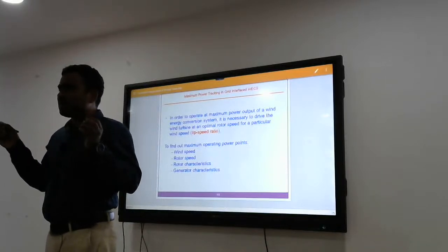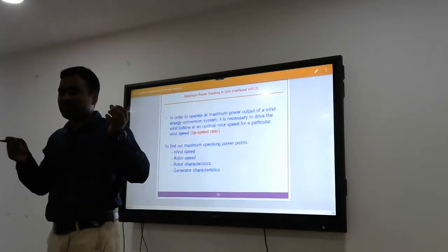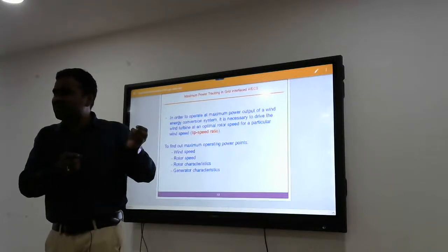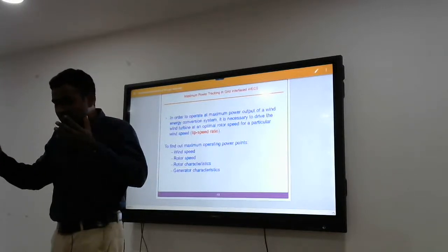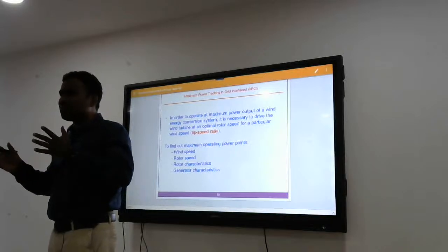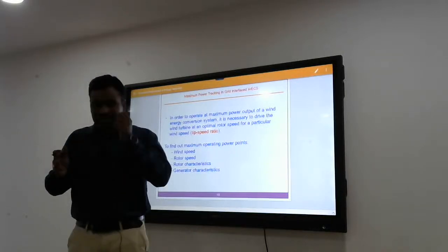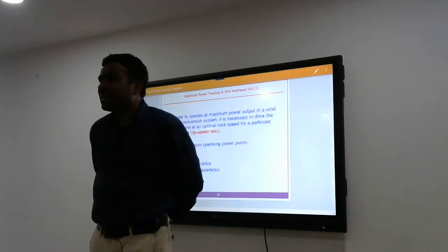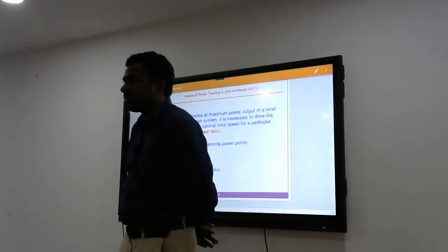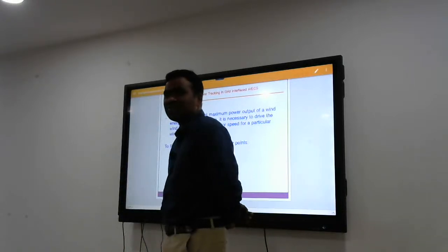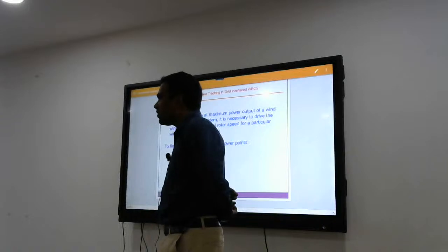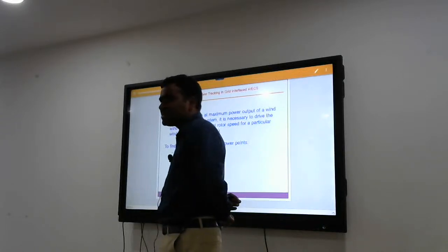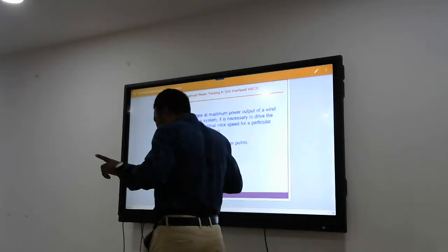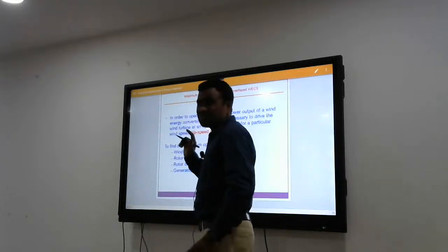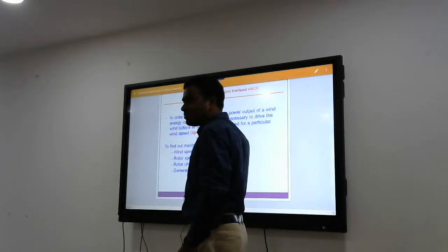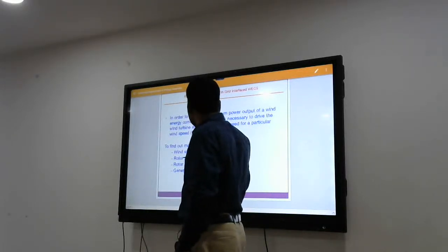If my wind speed is 12 meters per second, I am running at some particular speed. If my wind speed is 8 meters per second, I am running at a different rotor speed. So if my rotor speed is always changing, then my frequency is always changing. So now you will get variable voltage, variable frequency. Now to convert that into fixed voltage, fixed frequency, you need some power electronics converters. Okay, that's the main thing we are going to see, how this variable speed wind energy conversion system will be done.